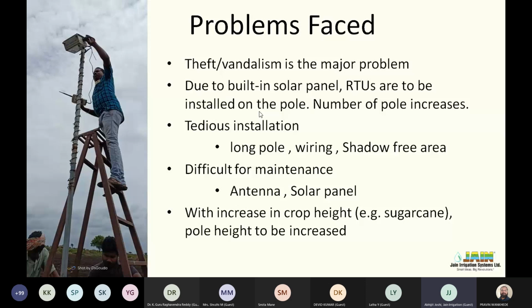Sometimes, even though the boxes were IP65 rated, we observed leakage issues, water ingress in the box, because it is open to atmospheric conditions. In heavy rainfall conditions, three years back there was unseen heavy rainfall in the Karnataka area, and we observed water ingress in several RTUs. We found this was due to assembling issues at the factory. If the assembling is not proper, some burrs remain, or it is not tightened properly, water slowly ingresses inside and damages the electronics. So these were the issues.